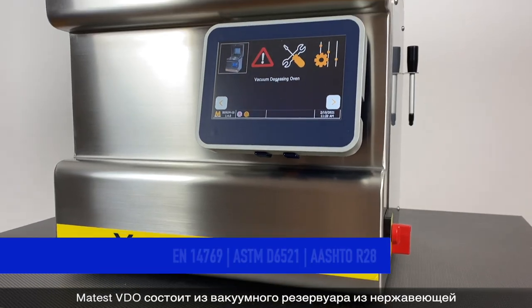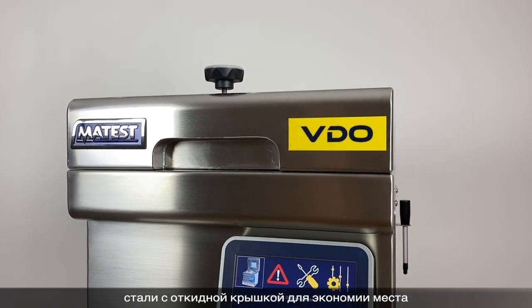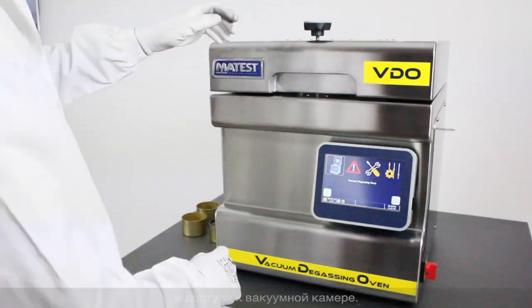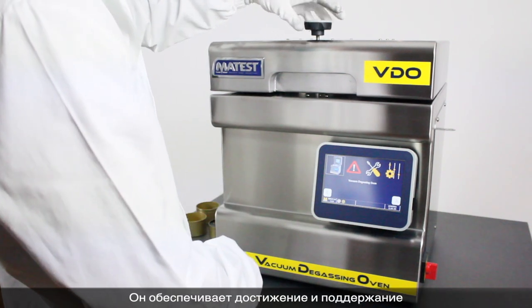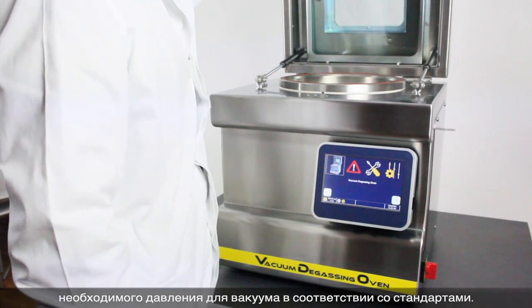Matest consists of a stainless steel vacuum vessel with a hinged lid to conserve space and access the vacuum chamber. It assures the achievement and maintenance of the required pressure for vacuum according to the standards.